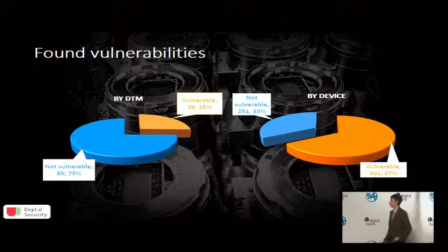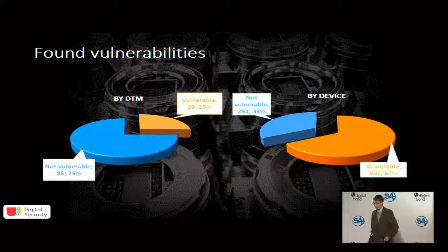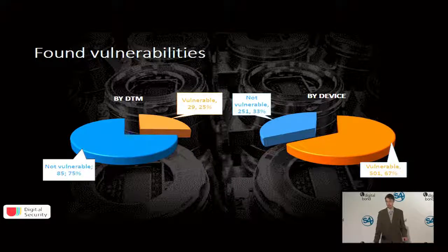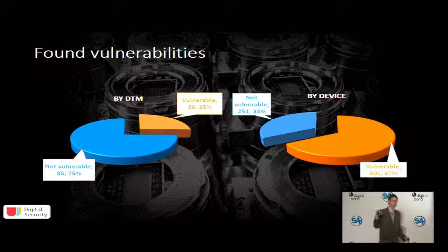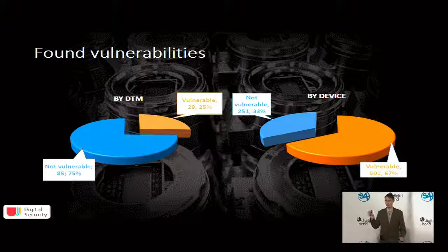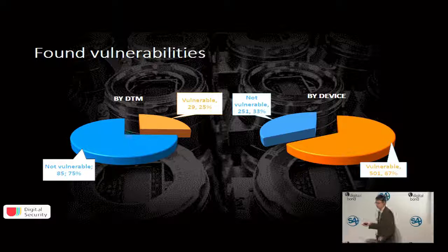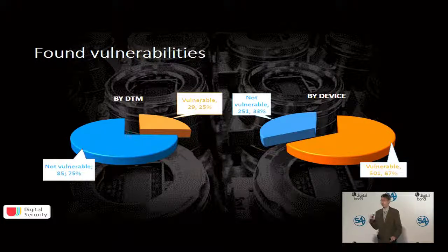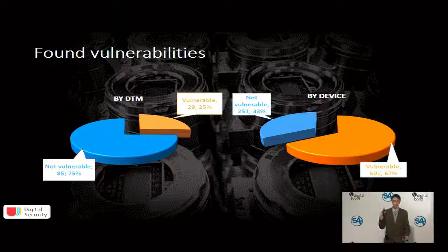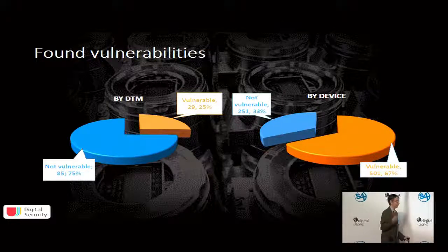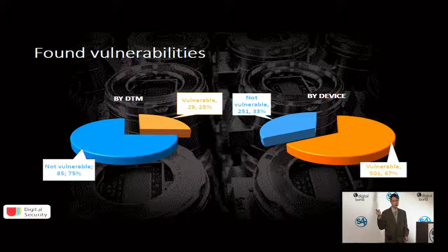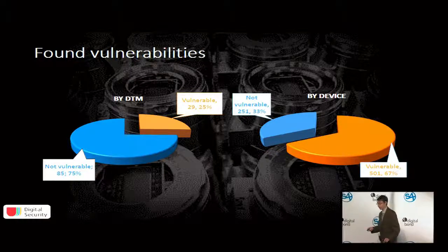Here are some nice diagrams. We have about 29 vulnerabilities. We have a bunch of errors, but not vulnerabilities. Here I only show vulnerabilities that could pose some risk to the industrial control system. I don't include found bugs; there are many bugs also. And these vulnerabilities affect 500 devices, so the components that have vulnerabilities work with 500 different HART transmitter devices.